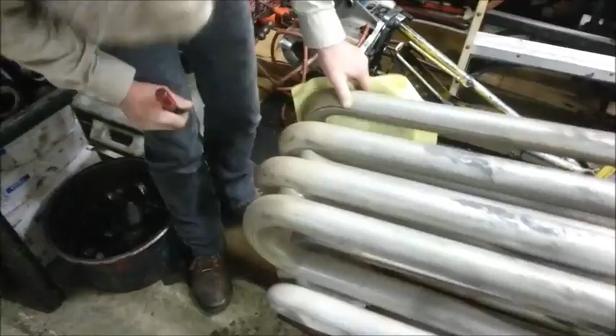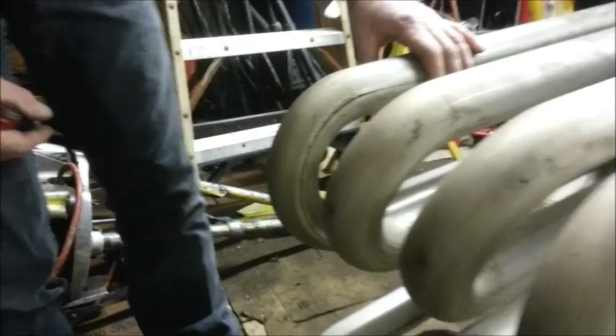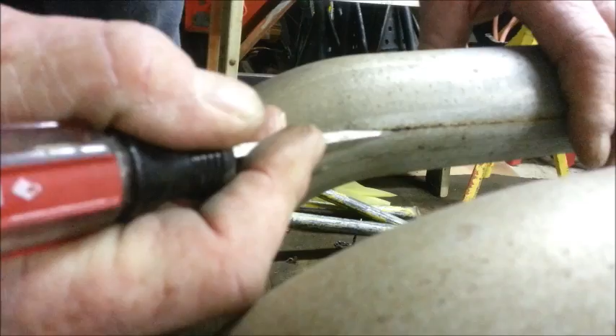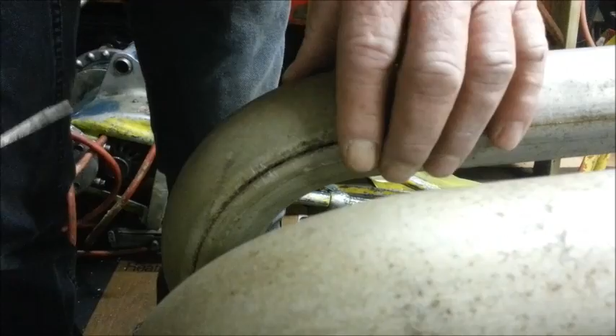Let's take a better look at this. I usually like to start with the seams, because it seems to be a weak spot on all manufacturers of heat exchangers. If you look around here, and as you come up close, you can see that this seam is here. Often we use a screwdriver just to check it because you can see what happens. And you can see that this heat exchanger all along there, the seam has corrosion taking place.